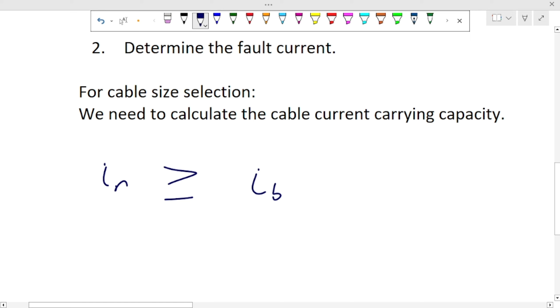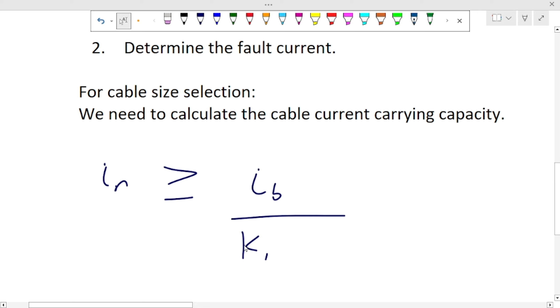What's the correction factor? Due to temperature, different temperatures will affect the conductivity of the wire and the cable, so we take that into consideration. So the correction factor for ambient temperature is K1. Then also correction factor K2, which is the correction factor for the British standard 3036 fuse.